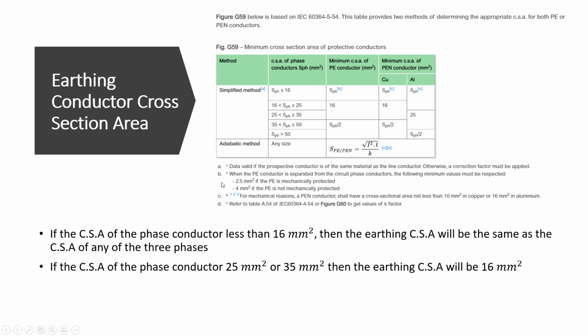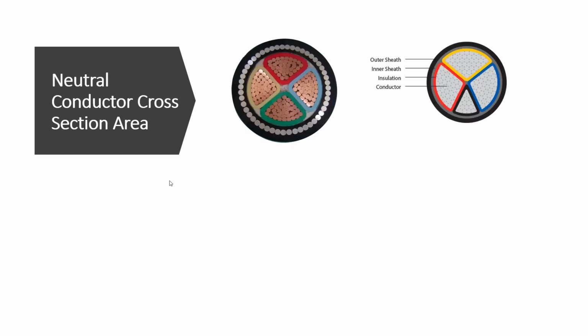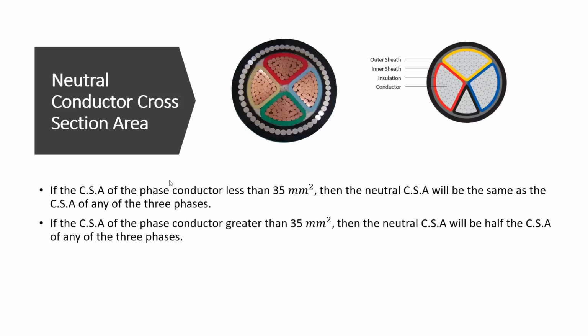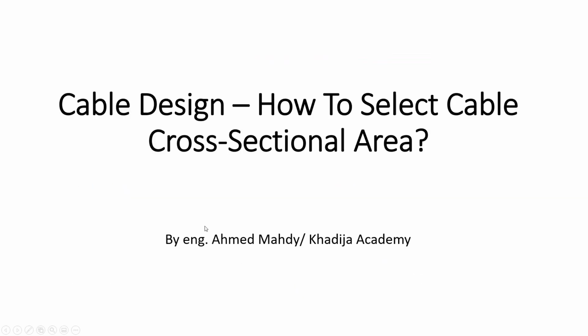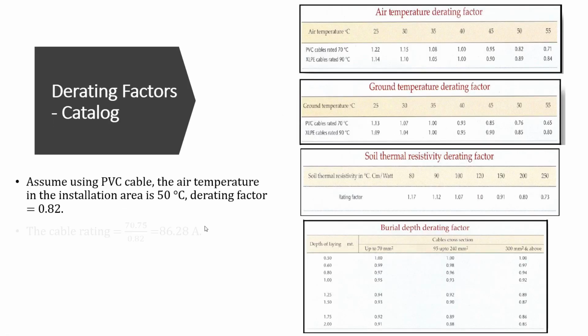You can go back to the previous lesson if you don't remember this. Now for the neutral, we said that if the phase size is less than 35 square millimeters, such as in our case, where we selected 25, then the neutral cross-sectional area will be the same as any of the phases. That's why we selected 4 multiplied by 25.